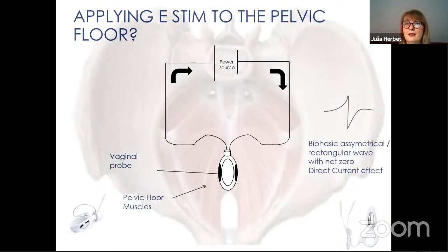anterior pelvic floor. So we have a power source, that will be your device. You have your leads that lead to the electrode. This is an example of like the Liberty probe that you can see bottom left. That would be positioned in the vagina. There are probes that you'll see coming up on the next slide that actually have rings around them, and then there are probes with longitudinal electrodes. And I do prefer the longitudinal electrodes because you've got a better chance of getting at that shelf of pelvic floor muscle and having your positive and negative effect to the stimulation. So we're trying to get a good contact, and contact's going to be important. We'll talk about that as we go through.